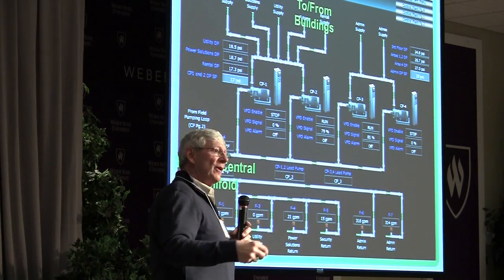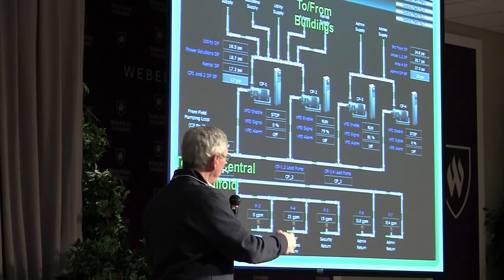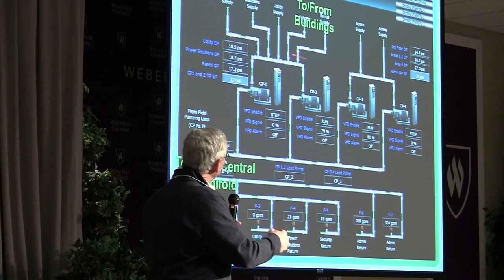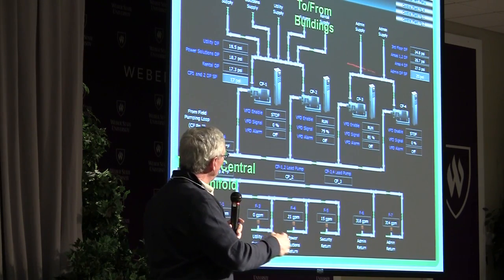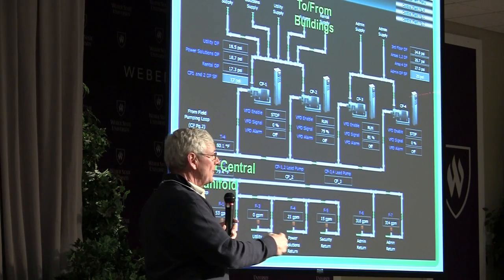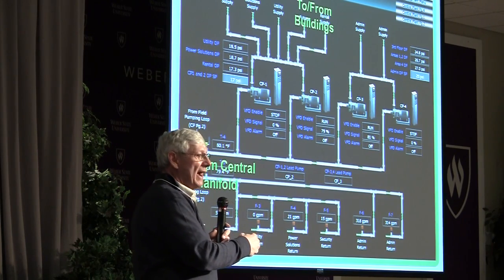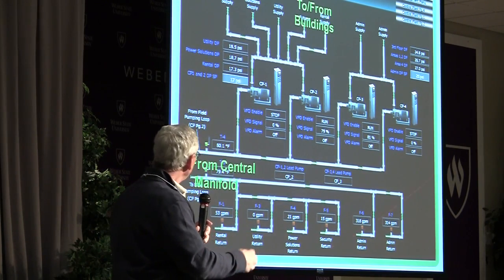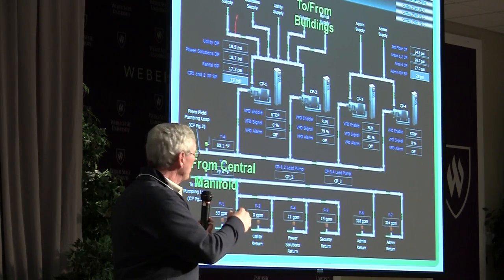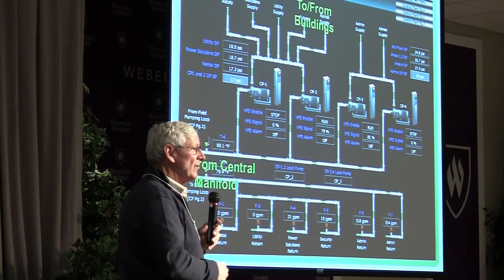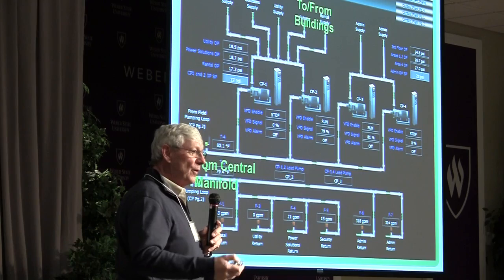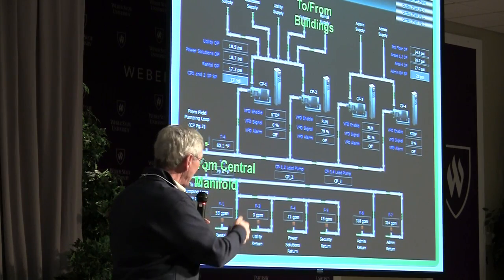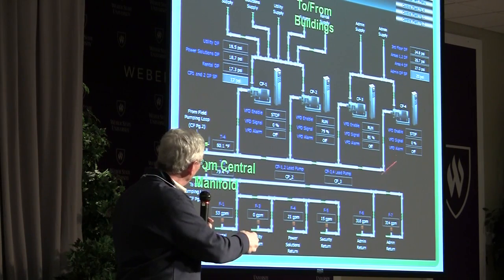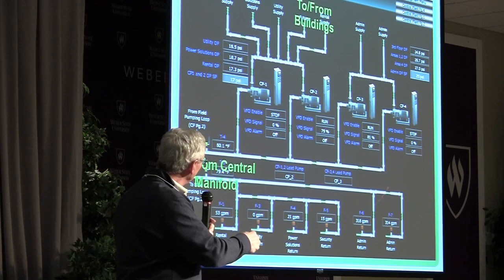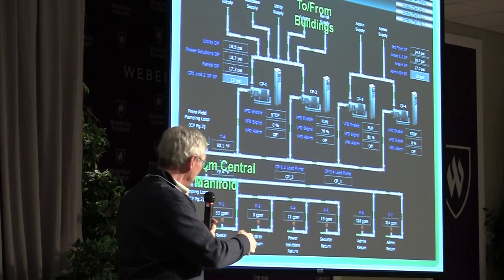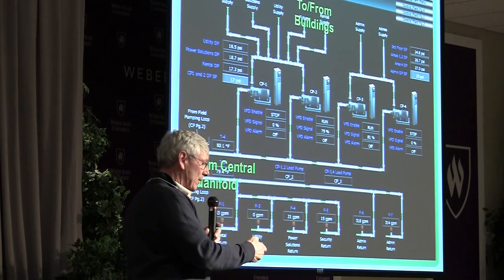So we don't turn the well fields on unless the loops and temperatures of the fluids going in and out of the building are either under 50 degrees or over 85 degrees. We just let that stuff go round and round, and the different buildings do whatever they need to do, taking energy out or putting it back in. Until that whole central loop system comes up above or below those ranges, we don't go back to the loop or the cooling towers.